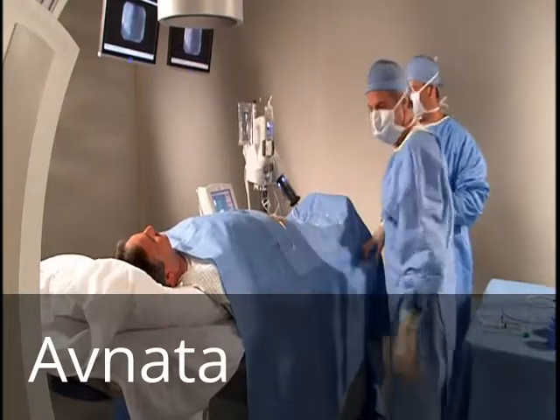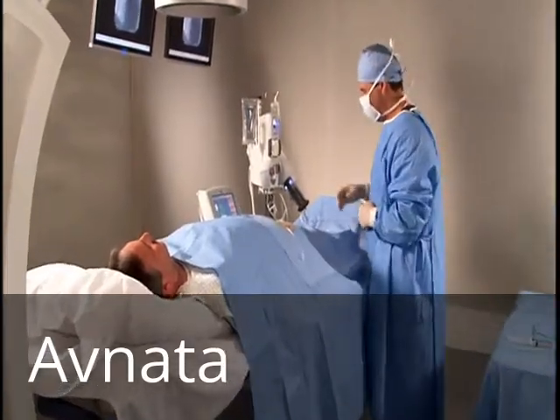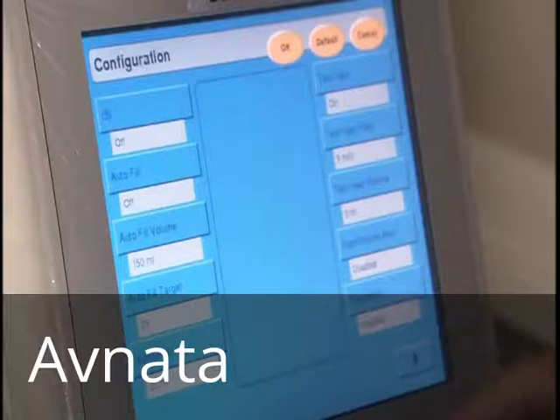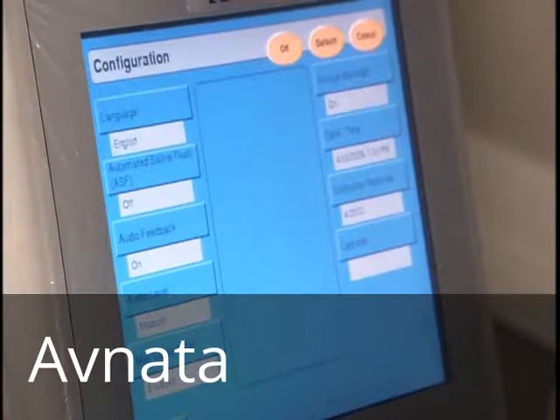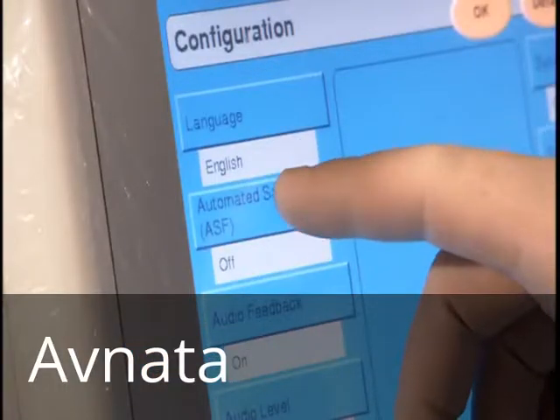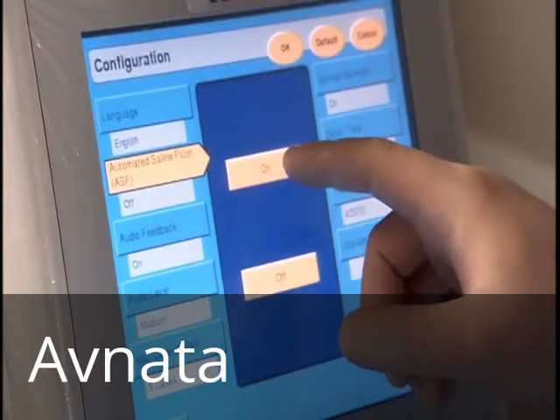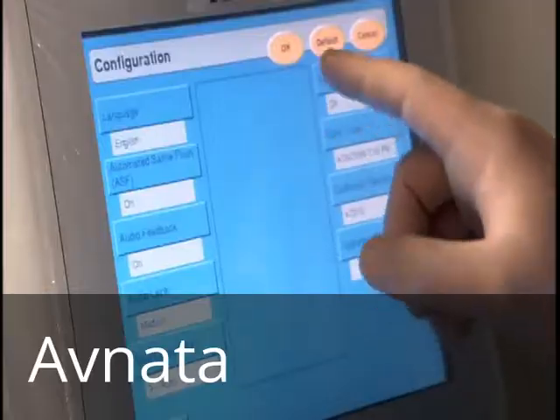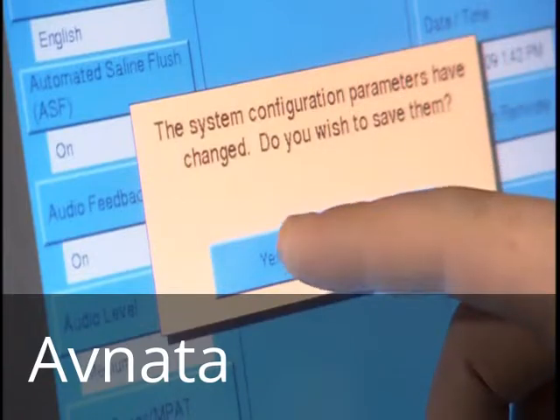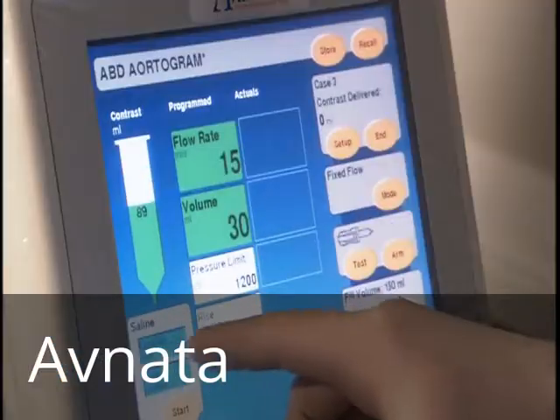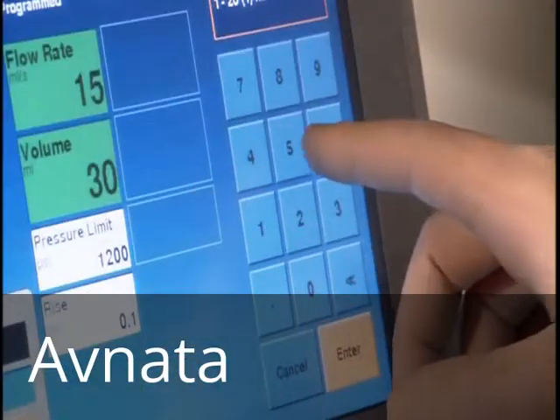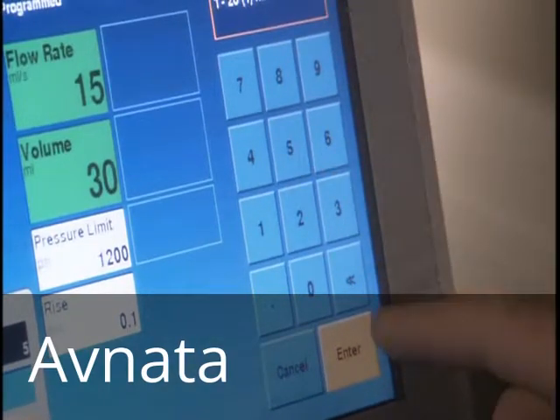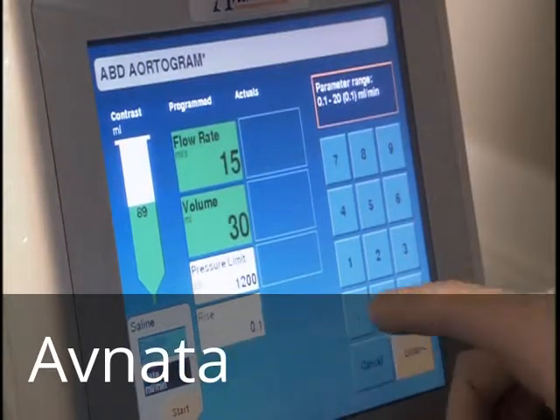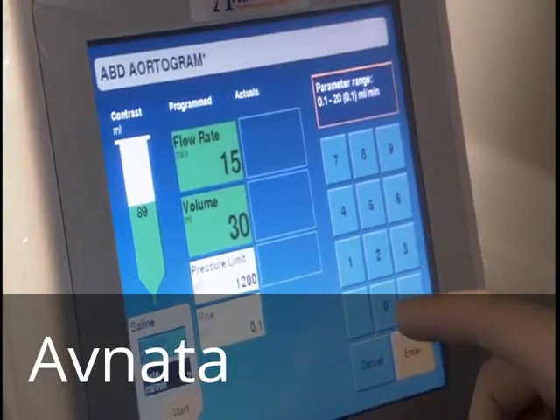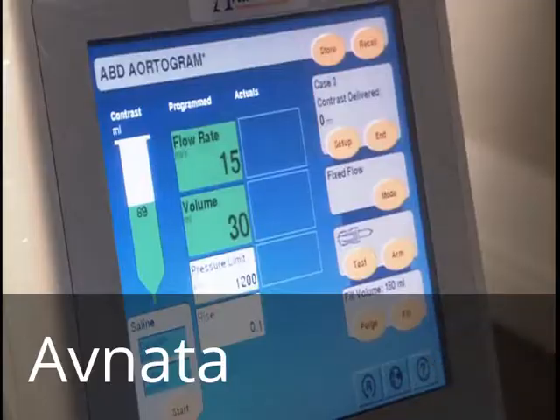Saline can also be delivered by activating an Automated Saline Flush, or ASF, function on the main protocol screen. This feature can be turned on or off via the configuration screen. ASF can be programmed to deliver saline during idle periods when contrast is not being injected. The duration of saline delivery can be programmed from 1 to 20 minutes in 1-minute increments, and the delivery rate from 0.1 to 20 milliliters per minute in 0.1 milliliter per minute increments.